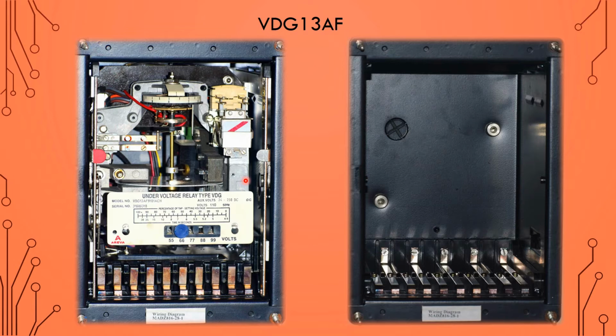That means we can remove it. That means when any relay is damaged or any fault comes inside the relay, we can replace the relay easily without changing any terminals or any connection of the panel. That means it is very easy. But in the case of a numerical relay, or that other relay, the microprocessor based relay, there you have to change the terminal, you have to use a screwdriver, you have to open the terminal, things like that. But in the case of electromechanical, this is very easy. Remove the relay and then insert a new relay inside the box.